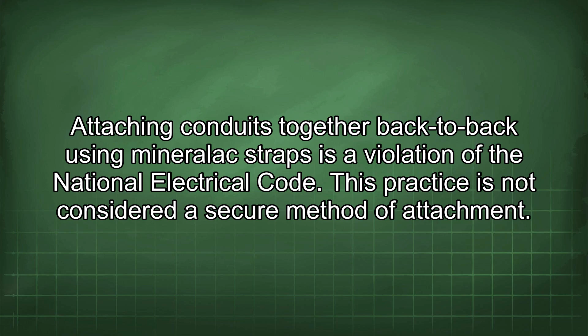Attaching conduits together back to back using mineralac straps is a violation of the National Electrical Code. This practice is not considered a secure method of attachment. According to the National Electrical Code, 2023 edition, Article 300.12(B), wiring methods and materials states conductors and raceways shall not be laid haphazardly in walls, floors, or attic spaces.